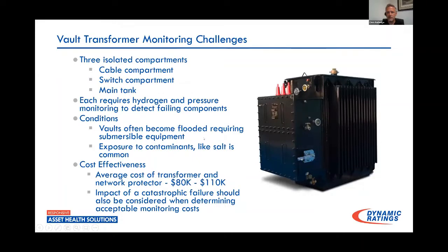So this is a typical network transformer. You're seeing some different designs coming out now. This is the traditional 3-compartment. So if we look here, this is our cable compartment. It only runs back to about this seam right here, so you get an idea of how small this compartment is. And you'll have your primary coming in here. We ran 13.2 on ours.